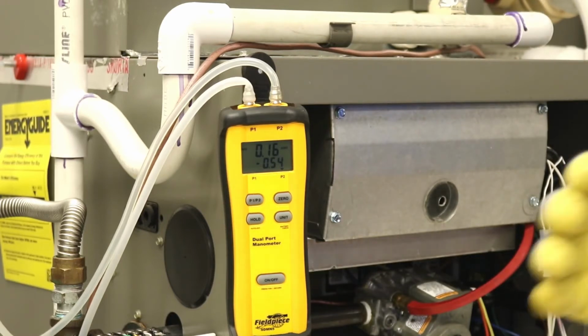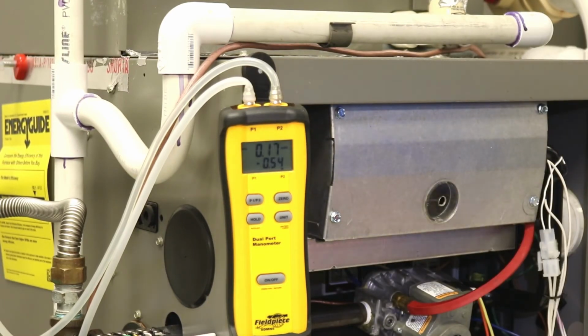And if you start inching closer and closer to that, you're going to want to start the process of finding out, okay, what's in the way? Could it be that I have a filthy dirty evaporator coil? Yes, that could be a problem. Could it be that I have a really dirty filter? Yes, that could be a problem. There are lots of different pieces of this puzzle that can cause static pressure to go way out of whack.